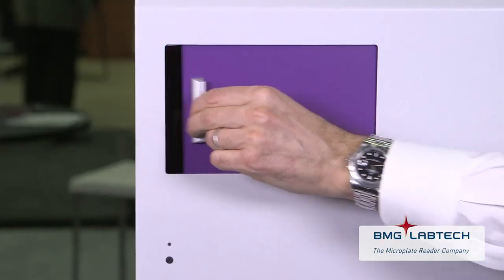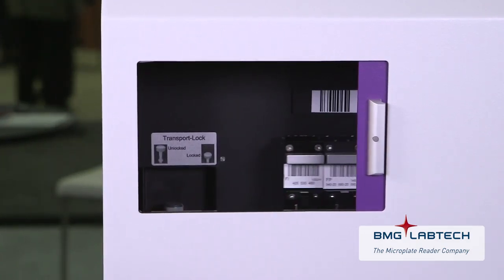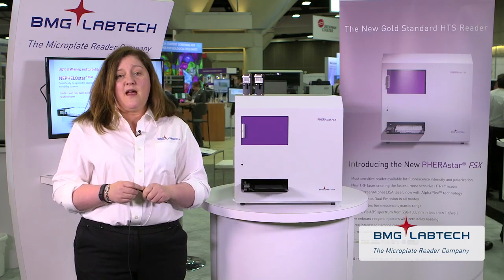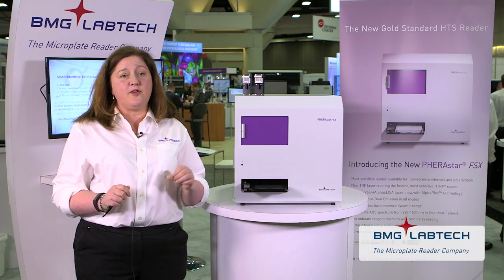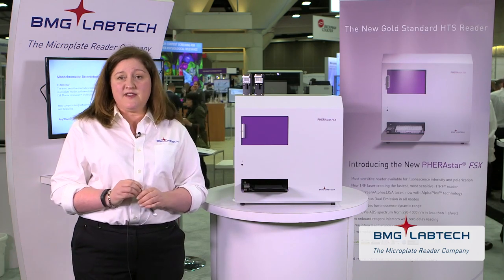I'm going to highlight just two features that affect leading assay technologies. Starting with HTRF or TR-FRET users: for flash lamp users, you will generally see an improvement in performance and sensitivity, and that may have an impact on signal to noise as well, dependent upon assay. But the biggest changes will come for those using our laser system. BMG LabTech have incorporated a higher frequency laser, which has a positive impact for both users with a throughput driver and also with a sensitivity requirement.